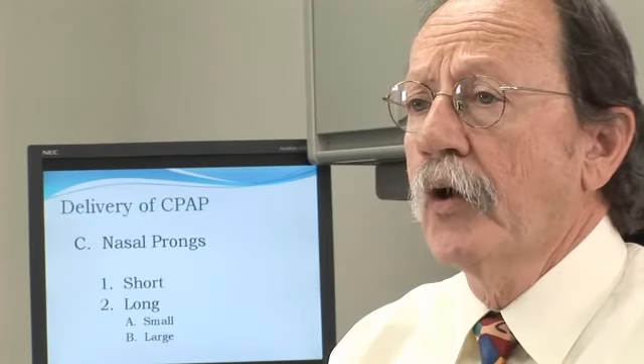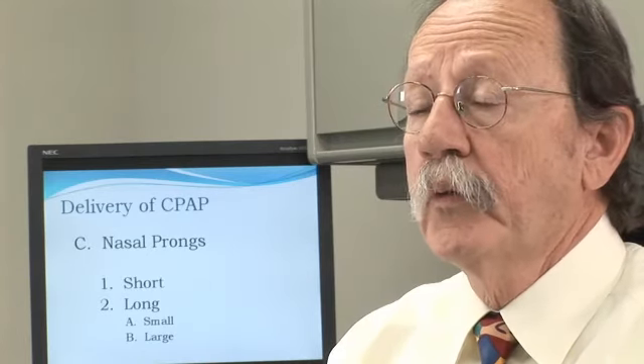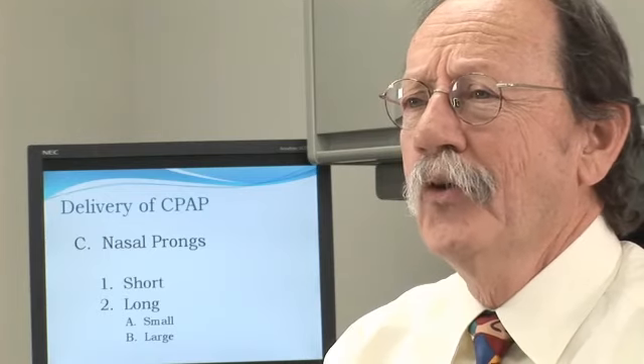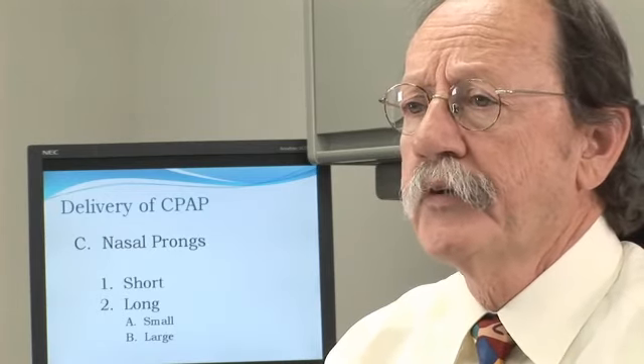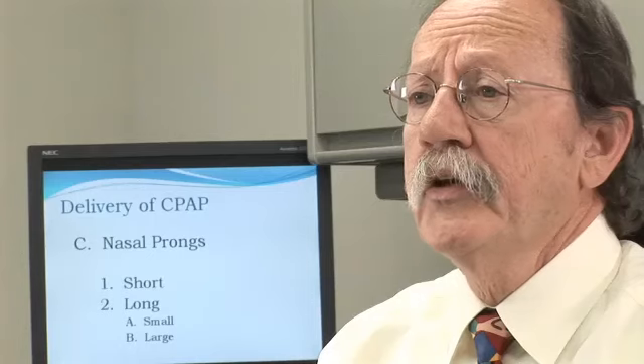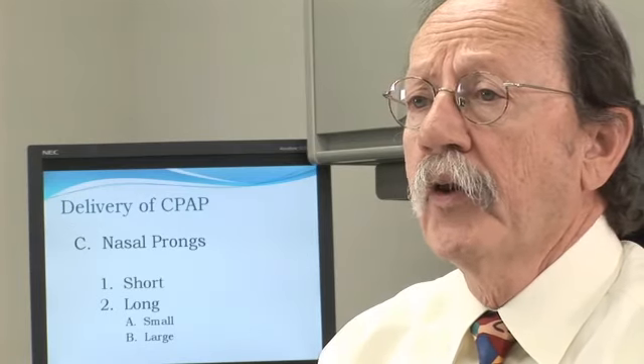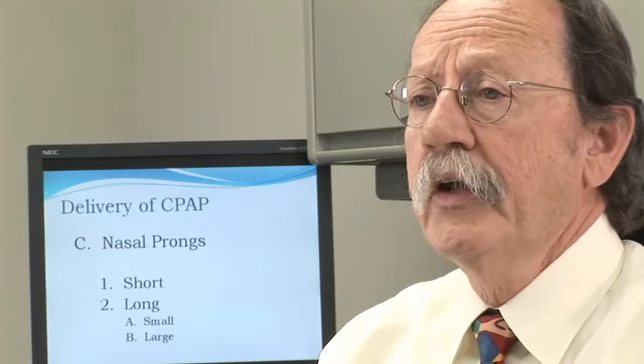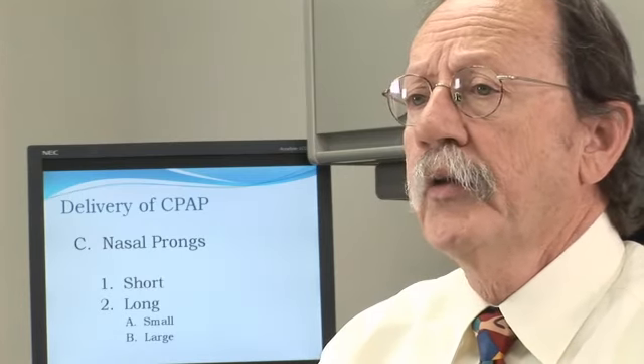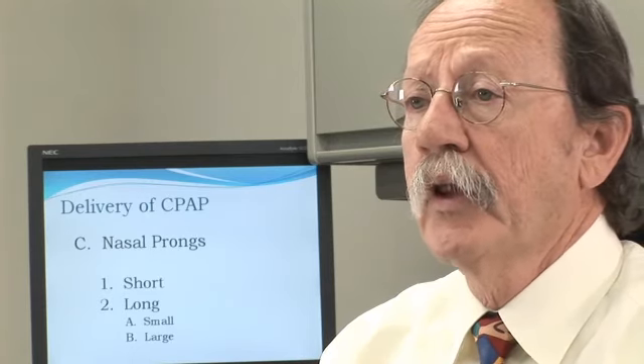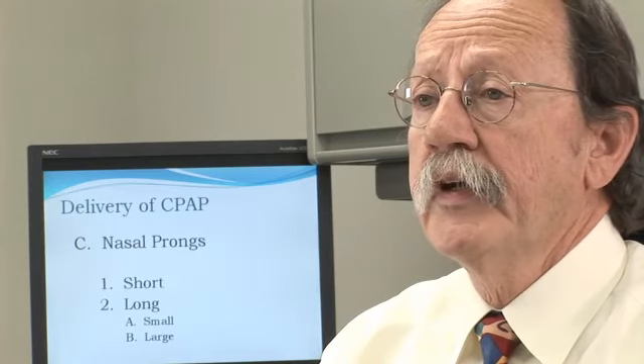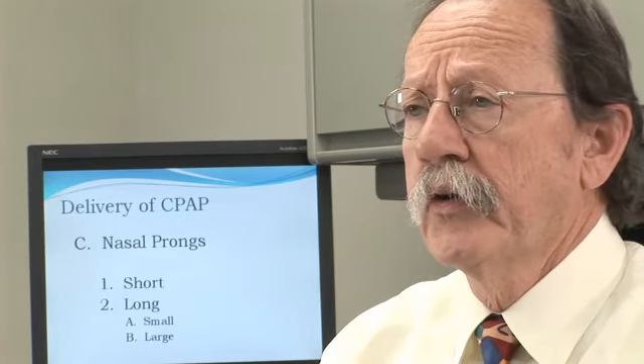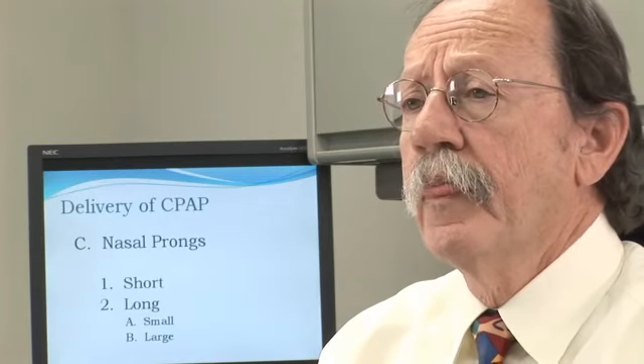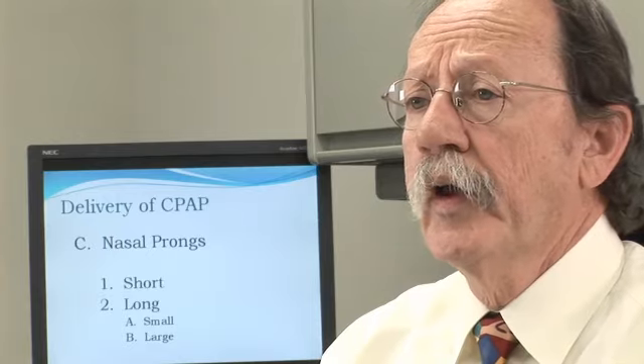The advantage to the long prongs is that they stay in the nose more frequently. So when the baby moves, you don't lose the positive end expiratory pressure with the CPAP, and that's beneficial because anytime you lose the pressure, you can de-recruit the lung. The problems with the long prongs are that you can build up a lot of mucus, and they can plug up, and it's not nearly as easy to see because you don't notice it until the patient isn't doing well, and then you pull the prongs out and you realize that they're plugged up, and so the baby's really not receiving oxygen or positive pressure under those circumstances. So if you're using long prongs, they do have to be taken out and looked at on a more frequent basis.